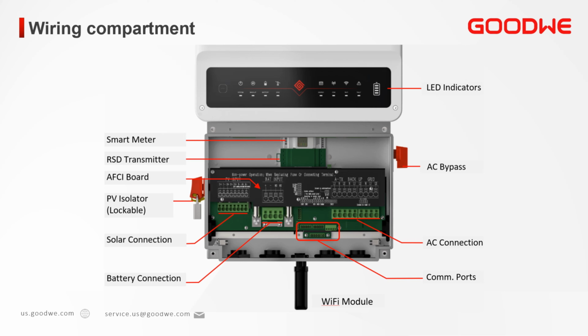On the outside left, you see the DC switch, which in this photo is showing a padlock. This is to comply with the lockout tagout. On the right side, you have the AC bypass switch, allowing the system to be put in bypass in case you need to power off the inverter but continue to provide utility grid to the backup loads. The inverter by default is in the normal position. From the top, we have the built-in meter as well as the rapid shutdown transmitter. I'll go into a little more detail on this later.